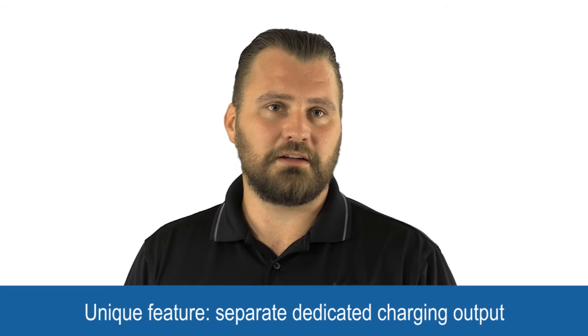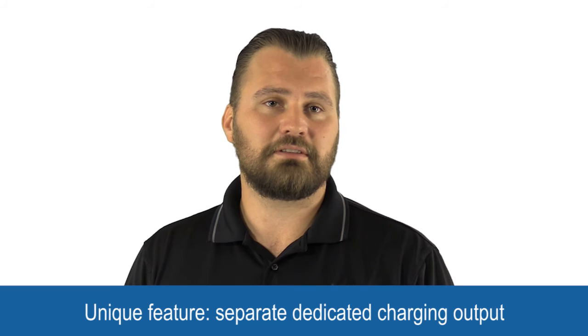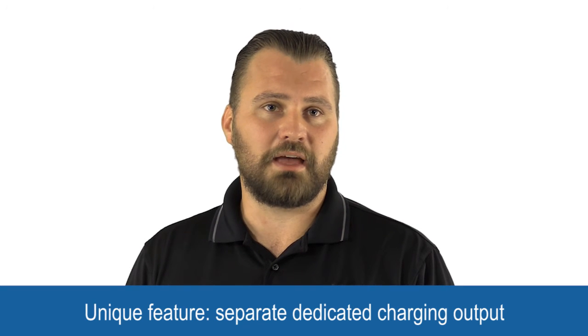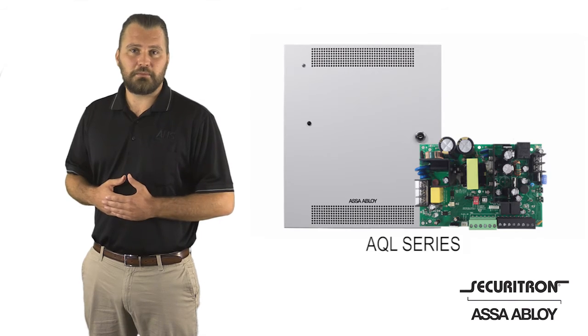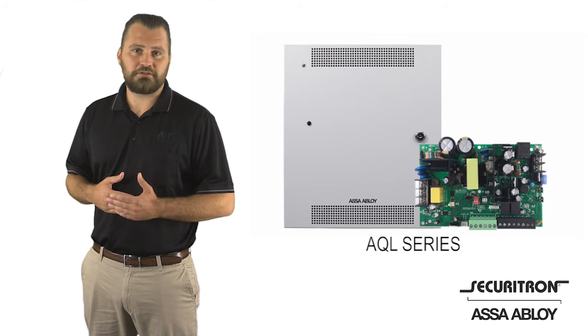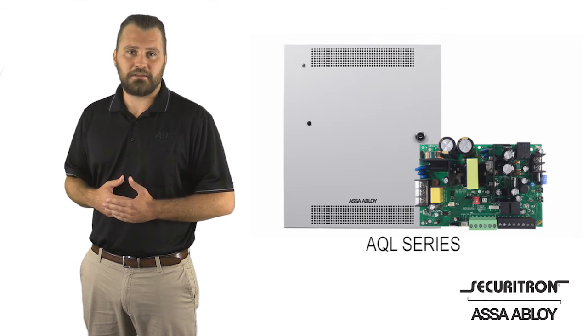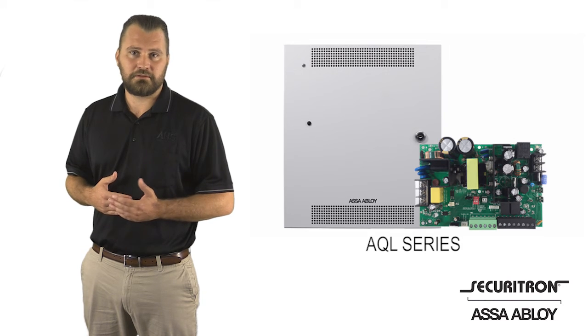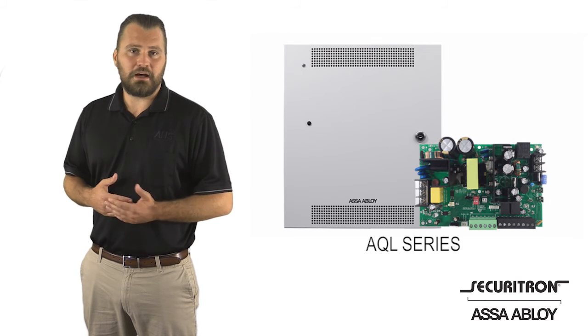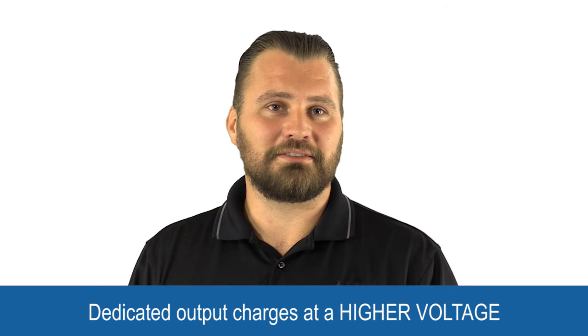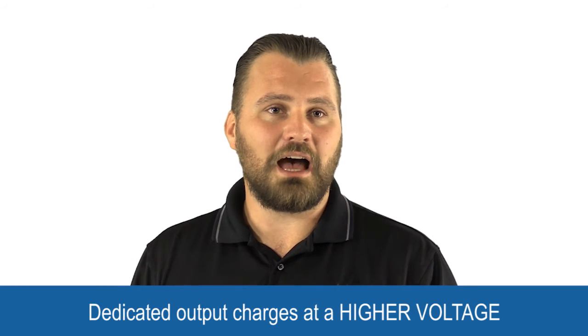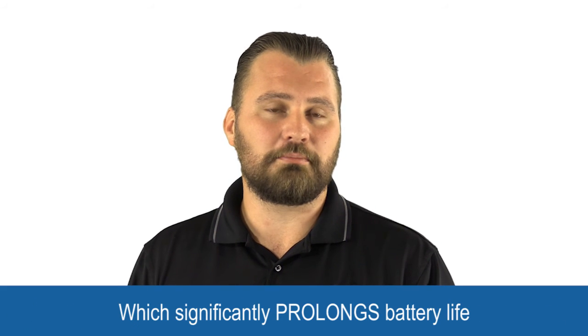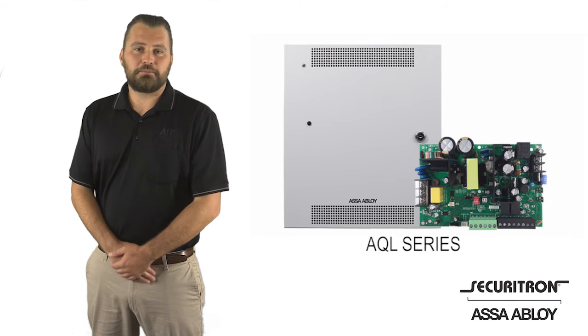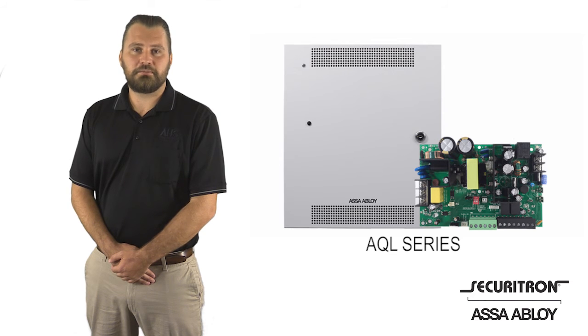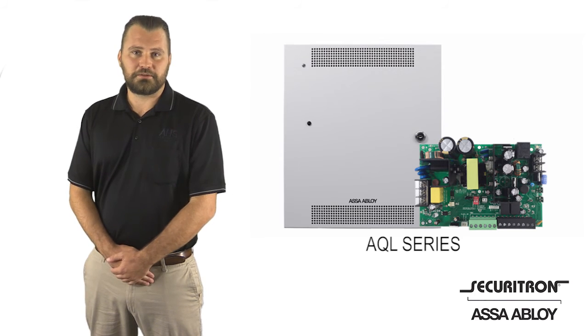A unique feature this line offers is that its units have a separate dedicated output to charge the backup batteries. This is unlike most competitors' power supplies that charge their backup batteries with the same output as the devices they were powering in the field, which can cause the lock to feel hot to the touch from overpowering. This feature is also important because the separate dedicated output charges at a higher voltage, which will significantly prolong the battery life. The battery is also protected from deep discharge or possible damage due to the low battery cutoff feature.